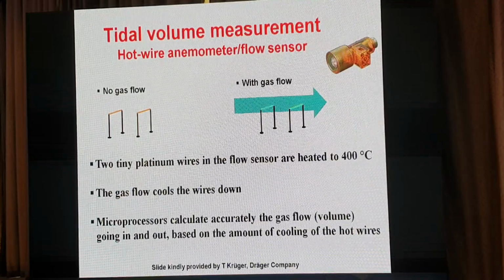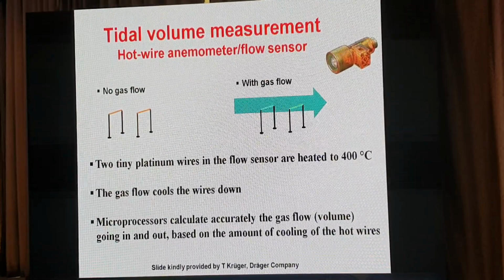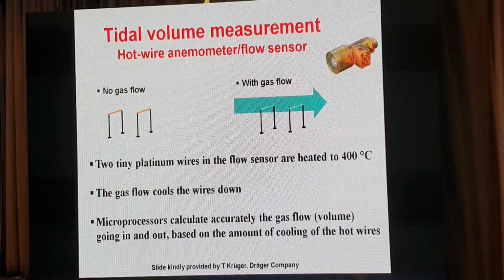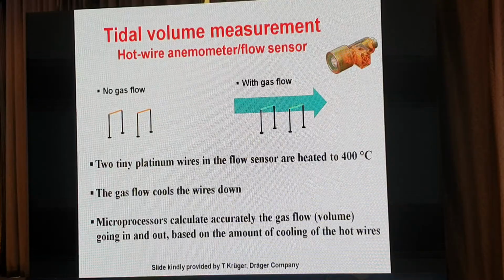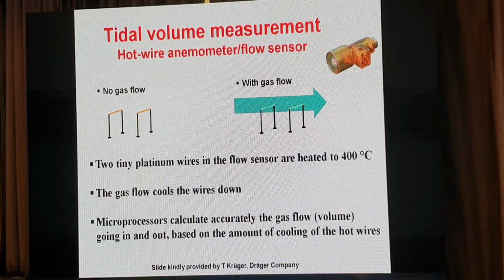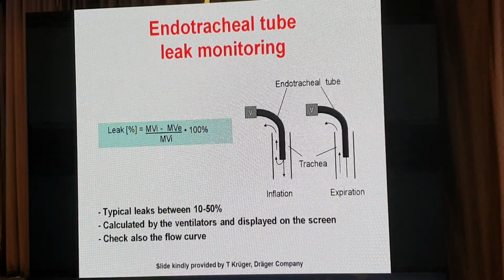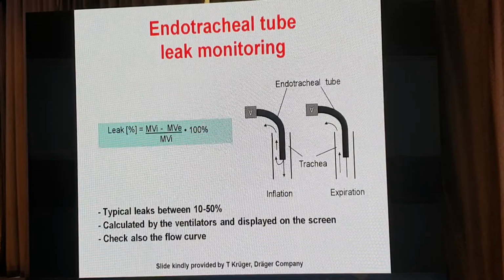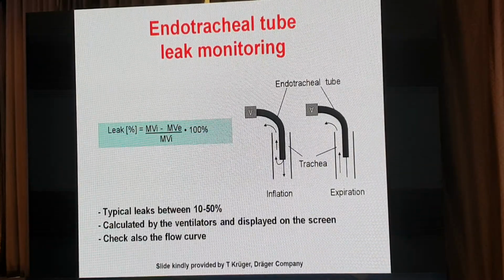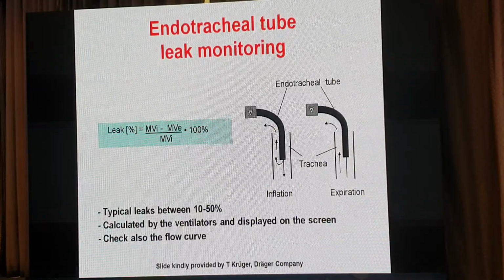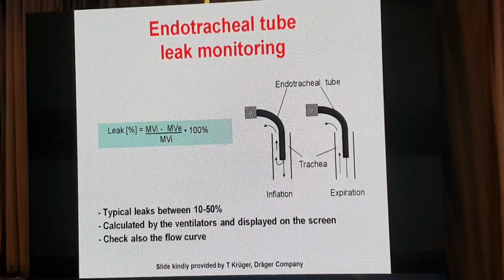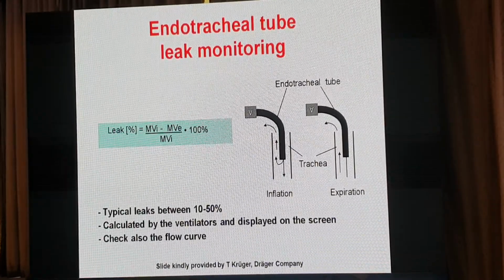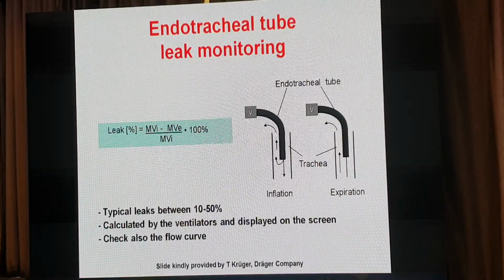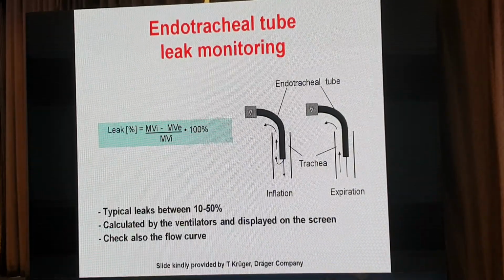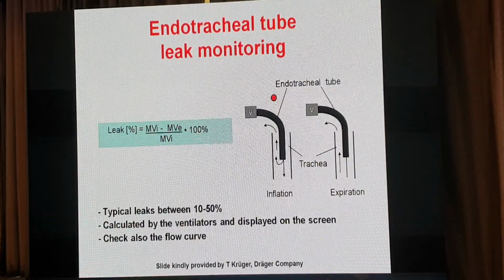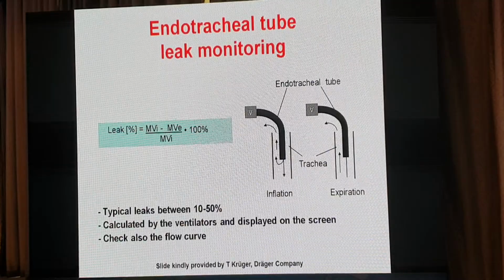So these tiny flow sensors placed at the Y-piece are a very important part of being able to do all these volume measurements, and the microprocessors are able to calculate the volumes continuously. What we also know is that there's always an endotracheal tube leak during ventilation of preterm infants. It may vary from 10 to 50% or even more, but we know that this leak is higher on inflation. When the ventilator is inflating the volumes, the leak is higher because there's higher pressure on the inflation. So the problem with the leak is mainly on the inflating part, where some volume is going out, whereas there is less leak on expiration.